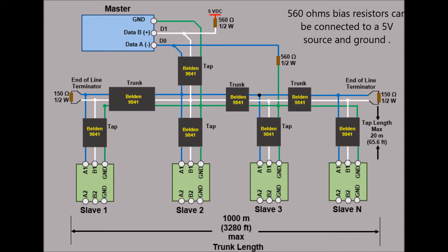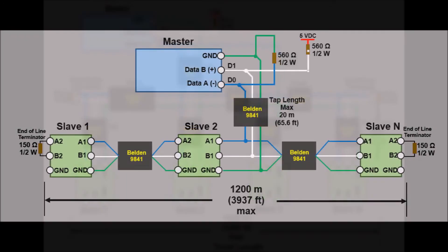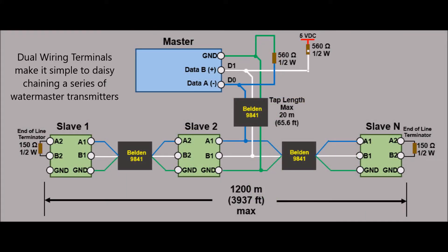A pair of 560 ohm resistors can be connected on the RS-485 balanced pair to bias the signals — a pull-up resistor to a 5-volt source on the D1 circuit and a pull-down resistor to the common circuit on the D0 circuit. The Watermaster has dual wiring terminals for RS-485 connections, providing a means of connecting the in and out bus cables for daisy chaining directly onto the bus.